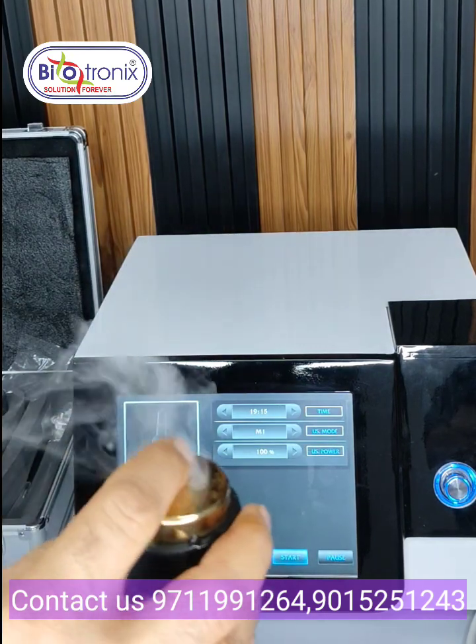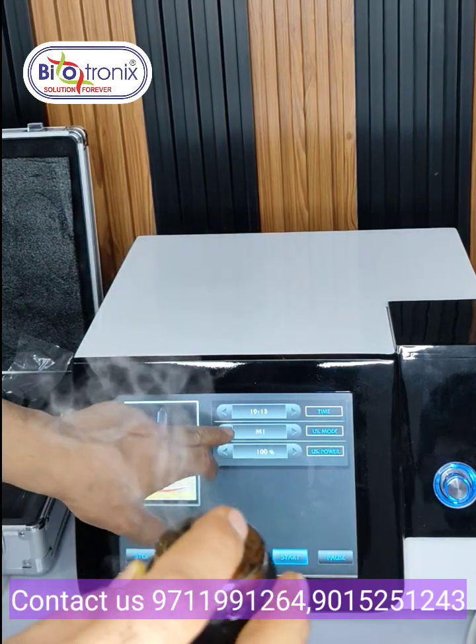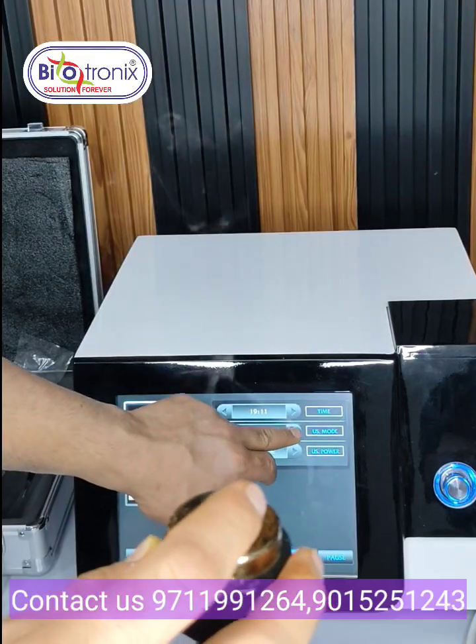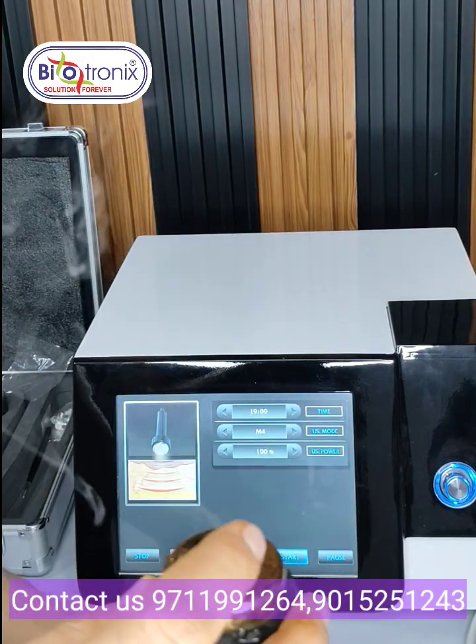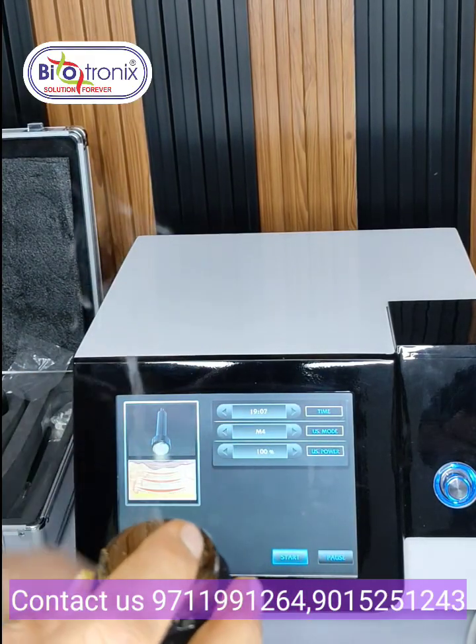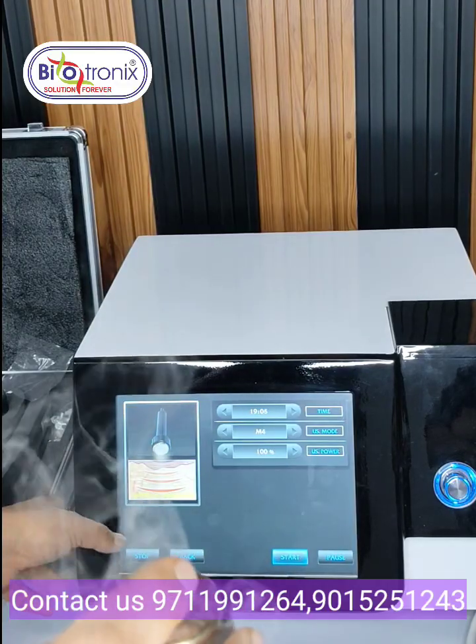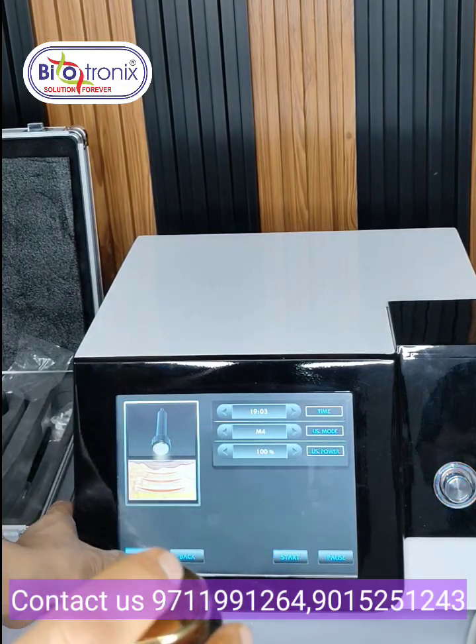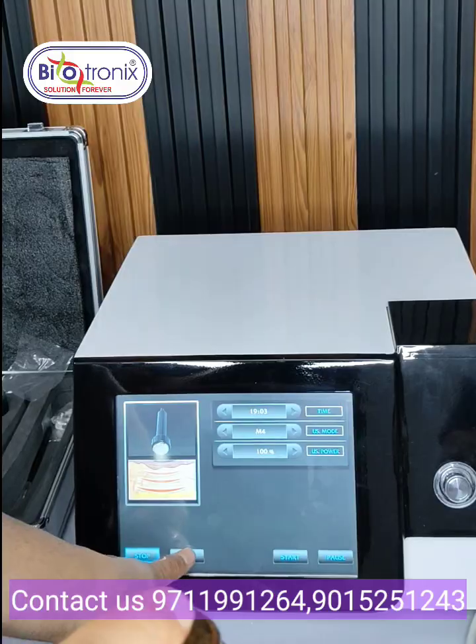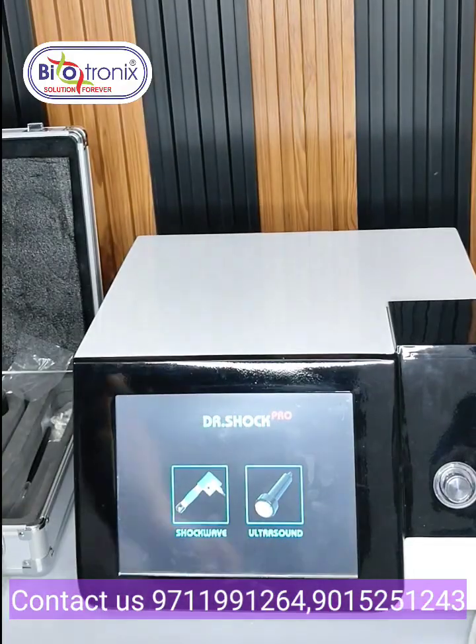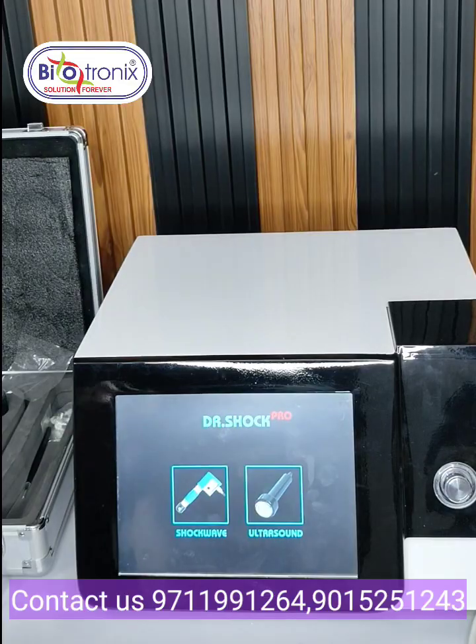So there are 5 different modes: continuous and pulse, auto mode, mode 1, mode 2, mode 3, mode 4. So these are the 5 modes. This is the demo of the ultrasonic section. Now I am stopping. Stop, back. So let me brief it. This is the combination of shockwave therapy and ultrasound. Shockwave is 0.5 bar to 12 bar, where the frequency is 1 to 22 hertz.